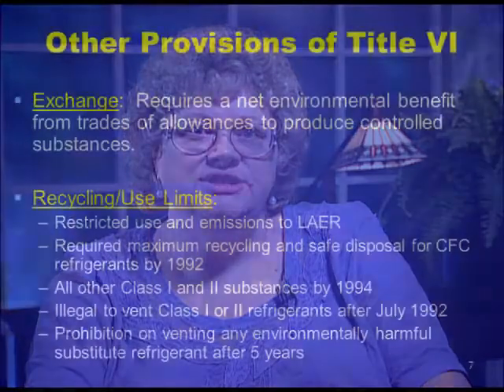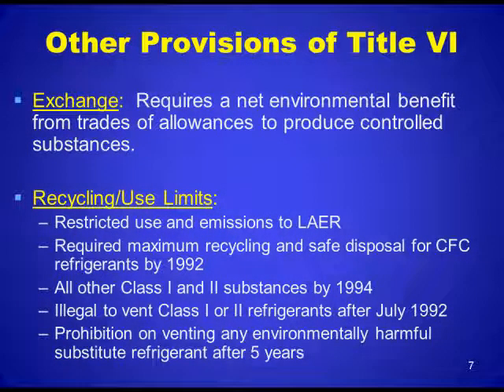There are some other provisions of Title VI. Regarding exchanges, it requires a net environmental benefit for trades of allowances to produce controlled substances. It restricted the use and emissions to the lowest achievable emission rate. It requires maximum recycling and safe disposal for CFC refrigerants by 1992, and all other Class I and Class II substances by 1994. It became illegal to vent Class I or II refrigerants after July 1992, and a prohibition went into place on venting any environmentally harmful substitute refrigerant after five years.